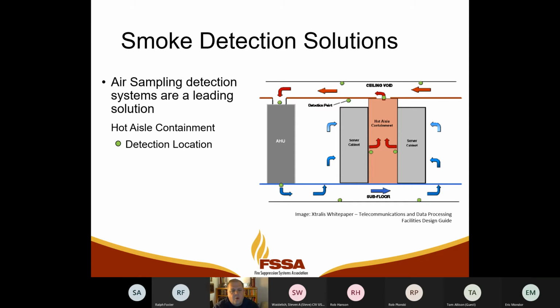But basically, what should be the fire alarm sensitivity of a sampling hole, and basically we're approximating what a spot smoke detector would be. I think it's like 1.5% obscuration at the hole, which when you dilute the air going back through an air sampling smoke detector, you actually have to be more sensitive than that at the detector than what you are at the hole to achieve that approximate sensitivity at the hole. So one good way that we do that, whether your standard is you want alarm at 1% obscuration or 1.5% obscuration or 2%, whatever it is, you take that value, you count out the number of holes in your air sampling network, and then you divide that concentration by the number of holes, and then that gives you a concentration value to use on your air sampling detector.